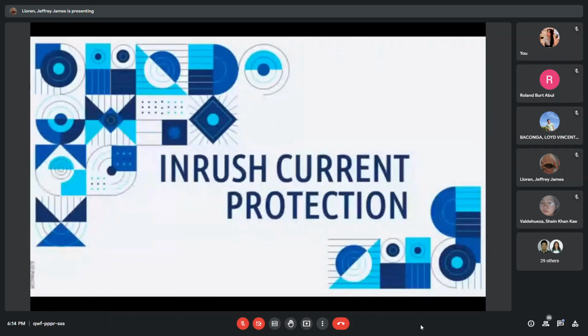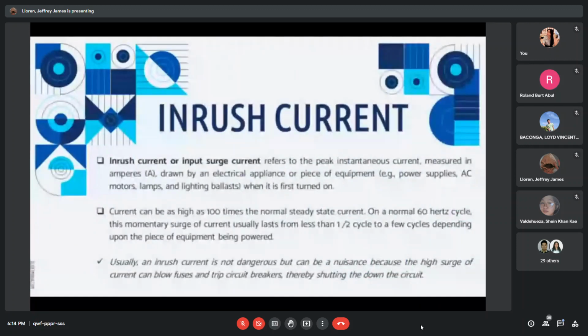Inrush current protection. So what is inrush current? Well, inrush current, or input surge current, refers to the peak instantaneous current, measured in amperes, drawn by an electrical appliance or piece of equipment such as power supplies, AC motors, lamps, and lighting ballasts when it is first turned on. The currents can reach up to 100 times their average steady-state value. On a normal 60 Hz cycle, this momentary surge of current usually lasts from less than 1/2 cycle to a few cycles, depending upon the piece of equipment being powered.